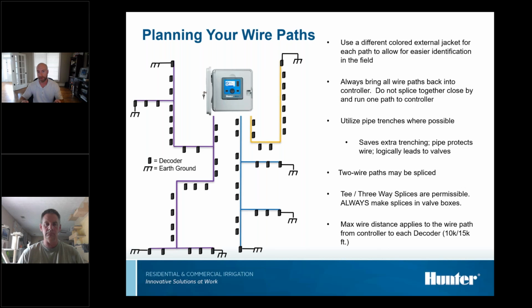If you've got, let's say, 200 valves all on the same 2-wire path, well, if you've got a problem somewhere in there, you really don't know where it is. There's no way to isolate it. But if you've got it split up into 75 a piece or something like that, you can sort of isolate each section of the system.